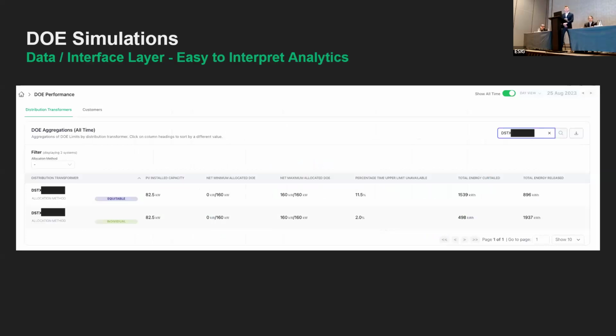A little bit hard to see, I acknowledge that. But on the far right, what we're doing is accounting for that curtailed and lost energy and the percentage of time that customers are curtailed under both schemes for each distribution substation, and then aggregating that across the whole network. The key metrics are the columns on the right: how much energy was curtailed, but then importantly, next to that, how much energy was actually released compared to a static export.